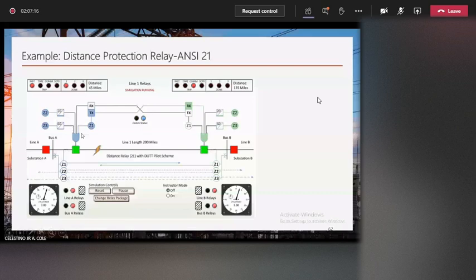So in this case, there was again a fault at 45 miles - close to 44, I just pressed slightly wrong. After 3 seconds, there was an event - the circuit breaker opened because Zone 1 detected the fault. However, compared to the first one, it didn't wait for the 3 seconds.